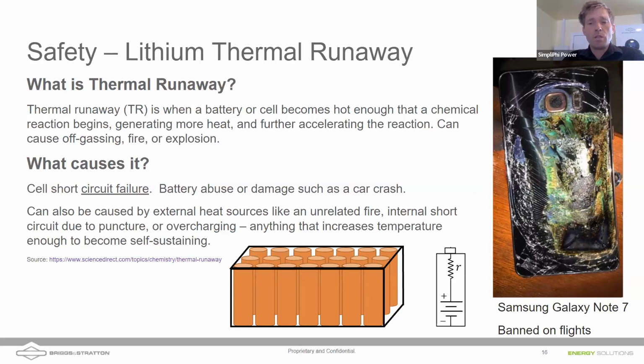That short circuit, as shown in this diagram of a battery, when a battery is discharged, there's some internal resistance. When it's discharged internally, maybe due to a short circuit, that internal resistance causes heat to build up inside the cell. If that cell gets too hot, it can rupture and give off an organic vapor from the electrolyte, which can be flammable. If that vapor gets hot enough and catches fire, in a larger battery module an individual cell catching fire can release heat to surrounding cells, causing those cells to go through the same process, essentially an unmitigated chain reaction.